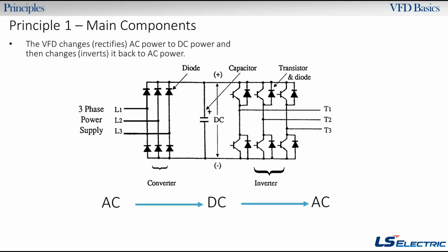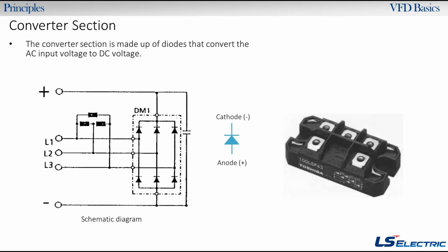So it's going from diodes to capacitors, okay? And then it's going back to AC because we have to run an AC motor, correct? We're all running AC motors on these drives, okay? So let's just look at the first section, which is the converter section, or the rectifier circuit. So this is made up of diodes. And if you look at these diodes, there's 1, 2, 3, 4, 5, 6. So there's 6 diodes. So if you've ever heard the term, like, I need a 6-pulse drive, I need a 12-pulse drive, I need 18-pulse, 24-pulse, whatever. This is what we're talking about.